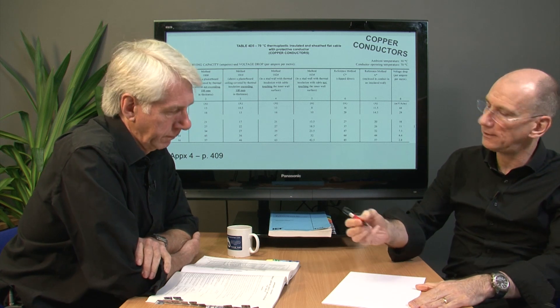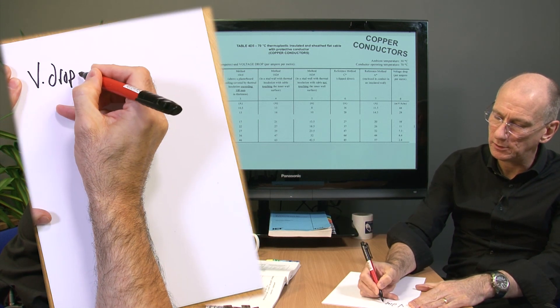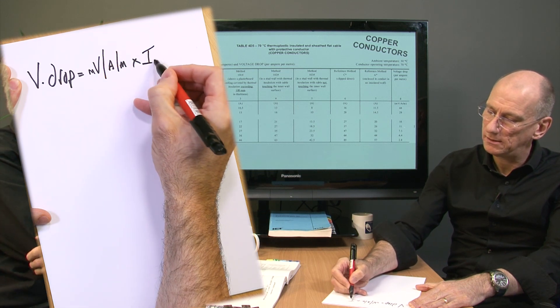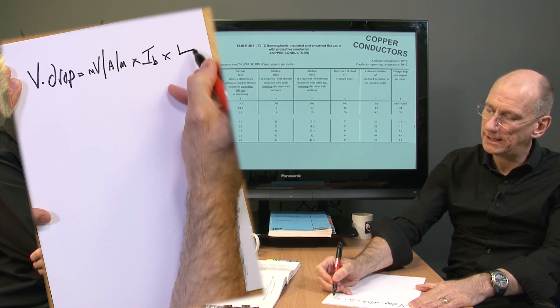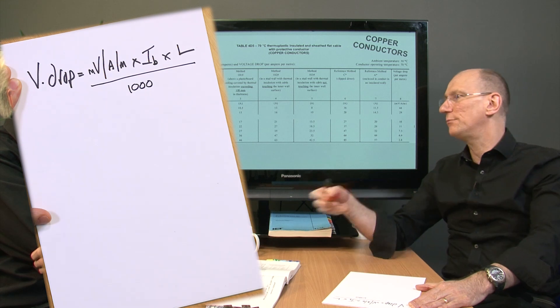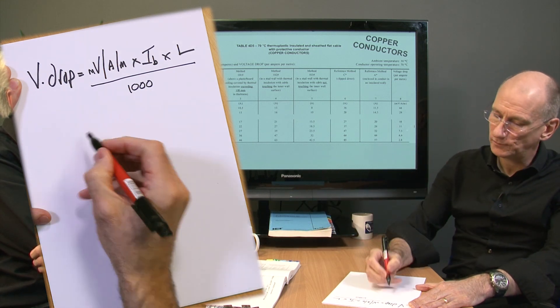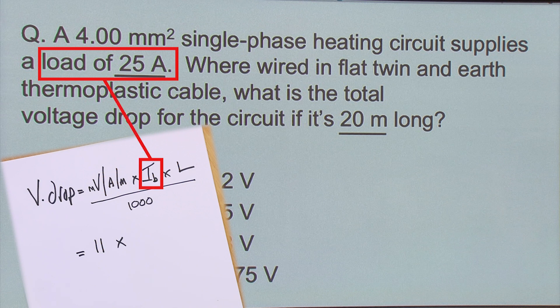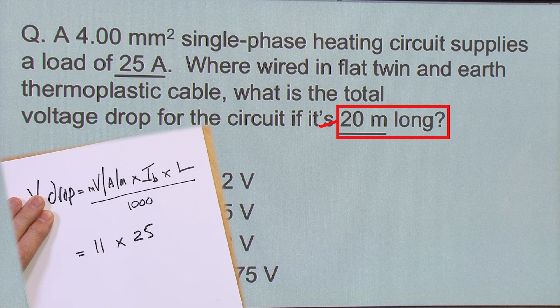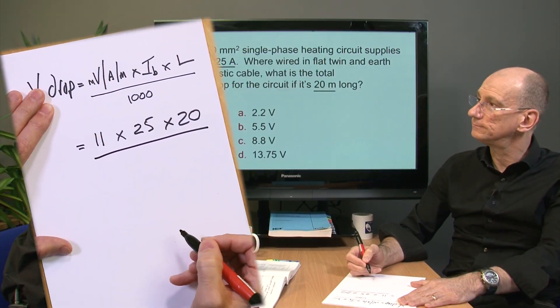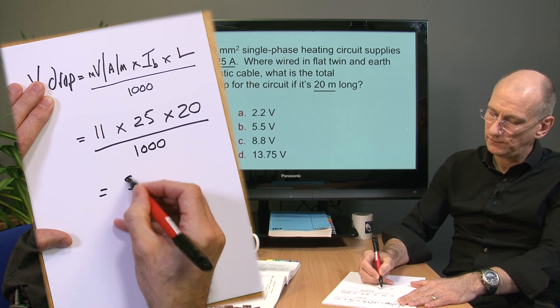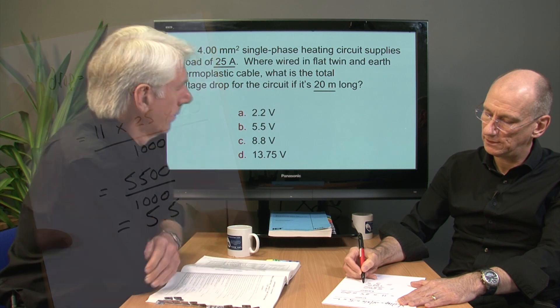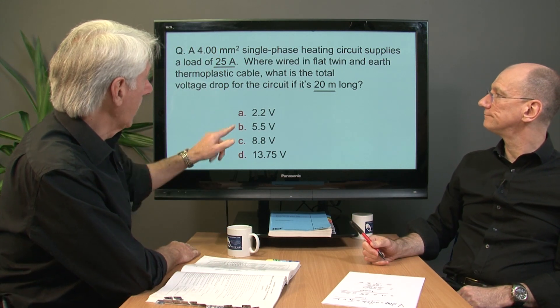All we need to do is input that into the formula. Voltage drop equals millivolts per ampere per metre, multiplied by IB (the load current), multiplied by the length — then divide all of that by 1,000, because we need to convert millivolts to volts. So: 11 multiplied by 25, multiplied by 20, divided by 1,000, gives us 5,500 over 1,000, and the answer is 5.5 volts. Looking at the question again, answer B is 5.5.